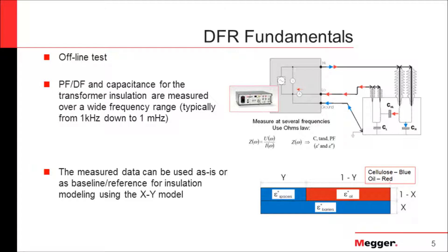Basically what we are doing here follows the same principle as power factor or dissipation factor testing. We are applying the voltage and measuring the current. We create two electrodes within the insulation system by shorting the high voltage side of the transformer, the low voltage side, with ground as the other electrode. Always remember that a good ground connection is quite important.